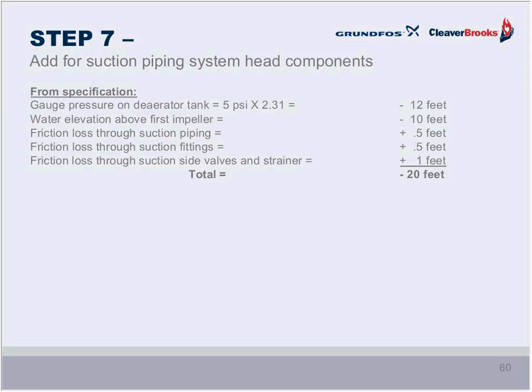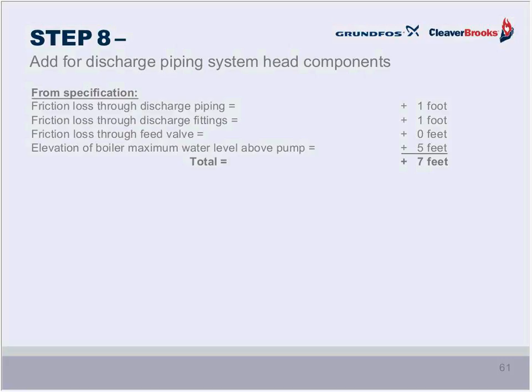Next, we have to take a look at all of the head add factors that influence the head in the suction piping system. You know, the gauge pressure on the DA tank, water level elevations, and some friction losses. And in this case, that all comes up to 20 feet. So we can check that item off our list. Then we have to add for the friction loss through the discharge piping system. And it's only 7 feet here. There's some friction loss, a little bit of elevation we have to worry about. But notice there's no feed valve.